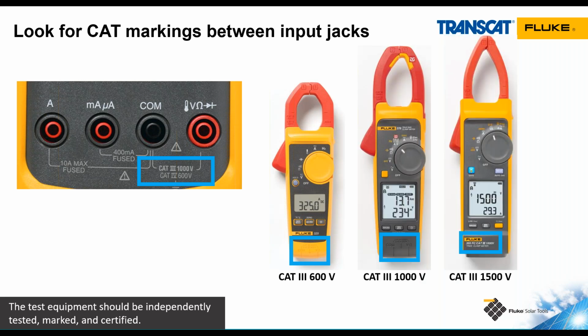Now I want to point out a series of clamp meters that we have at Fluke. The smaller one on the left is the 325 clamp meter, that's category 3 600 volt rated. The middle one is the 378, that is category 3 1000 volt rated, and then the 393 on the right, which is category 3 1500 volt rated. And these photos are relatively to scale, so you can see as the voltage rating goes up, the tool gets larger. And that's because there's more space inside the higher voltage tools to create a larger safety barrier for the technician so that they're not at risk when they're doing testing on these systems.